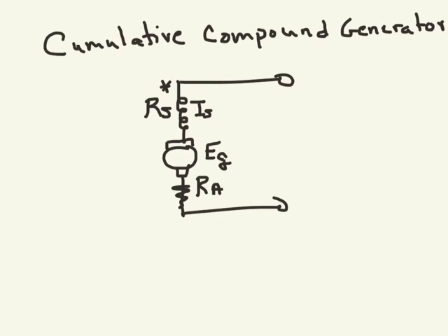If you remember in the self-excited situation, as we approached full load current, we had some issues with the field wanting to drop off at that full load current. We had some IA-RA losses, and therefore a terminal voltage loss, and therefore a field coil loss. So in this situation, we're looking at this field coil dropping off because we had it connected across the terminals before, and we were losing field.